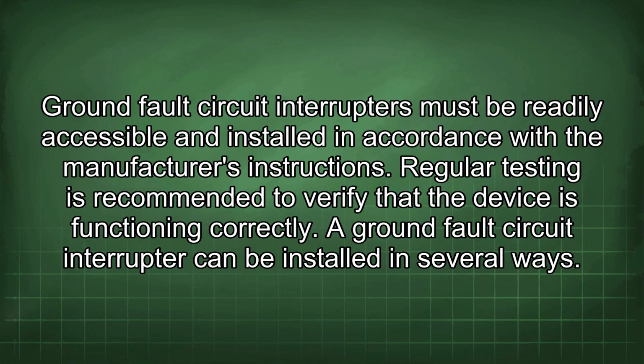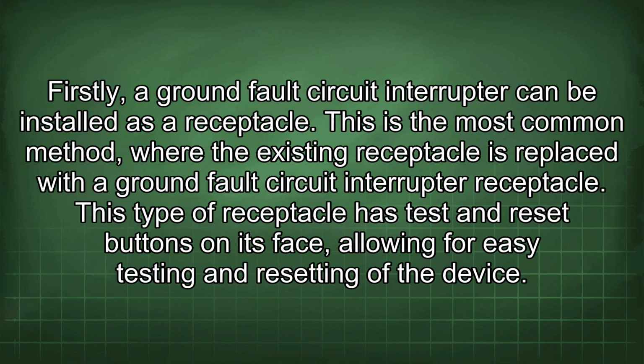A ground fault circuit interrupter can be installed in several ways. Firstly, a ground fault circuit interrupter can be installed as a receptacle. This is the most common method, where the existing receptacle is replaced with a ground fault circuit interrupter receptacle. This type of receptacle has test and reset buttons on its face, allowing for easy testing and resetting of the device.